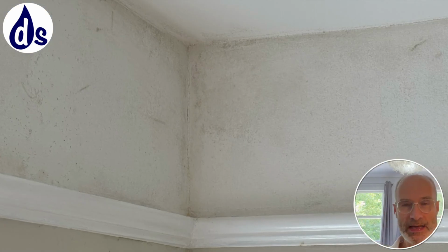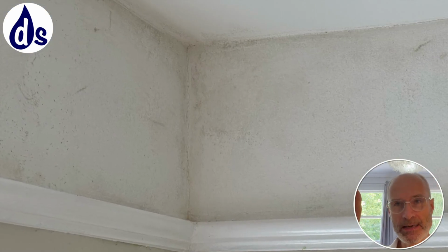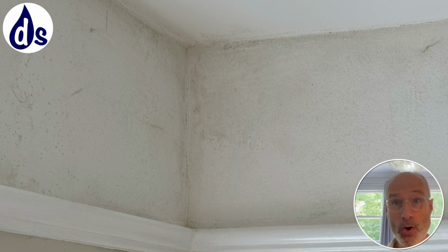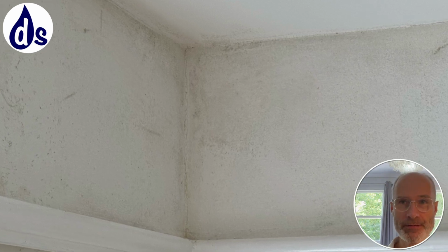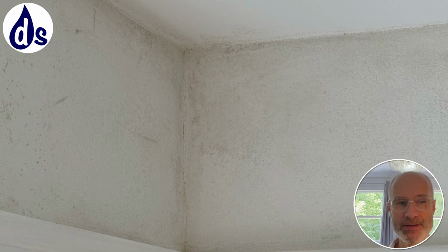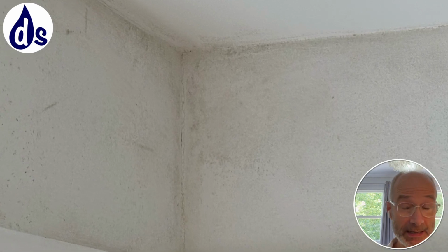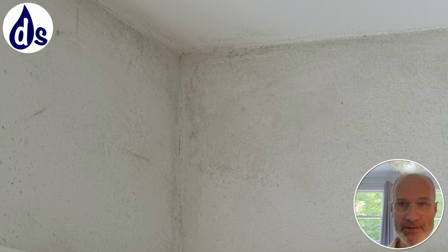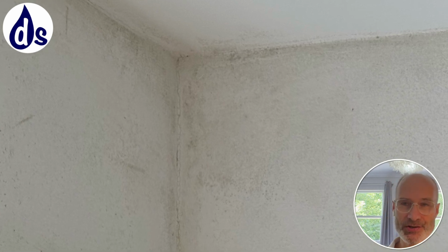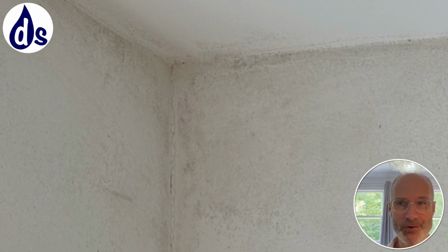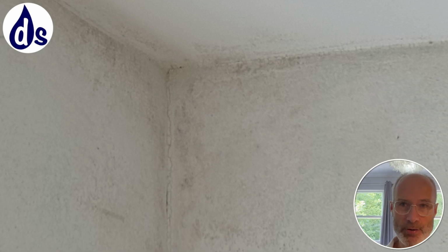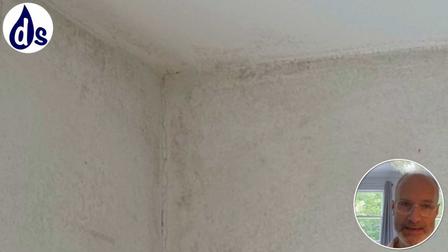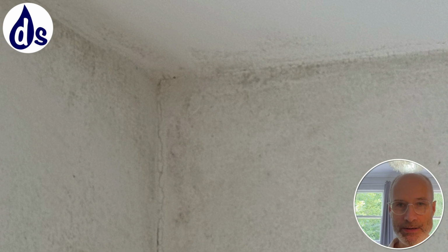So in this property, we have two different types of dampness. One is around the external walls, in particular in the corner where we can see mold. Mold grows in the same sort of areas as condensation. It's caused by excess vapor, made worse by heat loss in the corners, the lack of airflow, the increased external surface area, but it's still caused by excess vapor. That's the primary cause of mold, and it's made worse by heat loss.